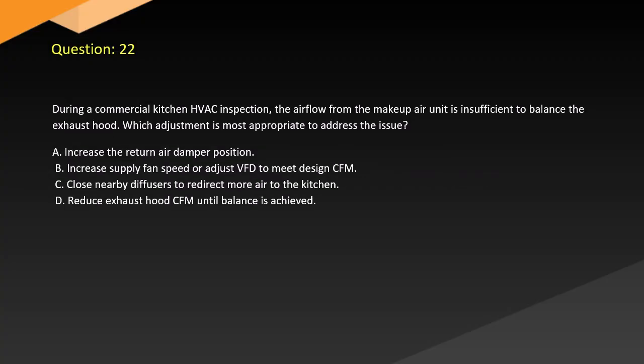Question 22. During a commercial kitchen HVAC inspection, the airflow from the makeup air unit is insufficient to balance the exhaust hood. Which adjustment is most appropriate to address the issue? A. Increase the return air damper position. B. Increase supply fan speed or adjust VFD to meet design CFM. C. Close nearby diffusers to redirect more air to the kitchen. D. Reduce exhaust hood CFM until balance is achieved.